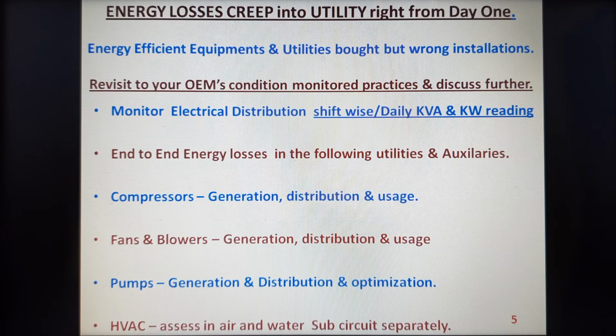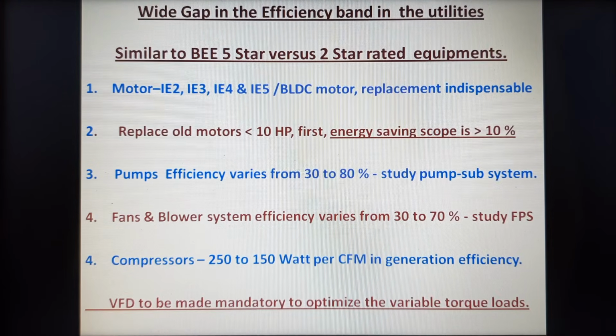at the process side. On the HVAC side also we have to look into the air circuit and water circuit separately, and definitely there is a lot of scope in the HVAC segment for excellent energy savings. There is a wide band of energy or efficiency in the utilities. This is similar to 5-star versus 2-star rated equipment.